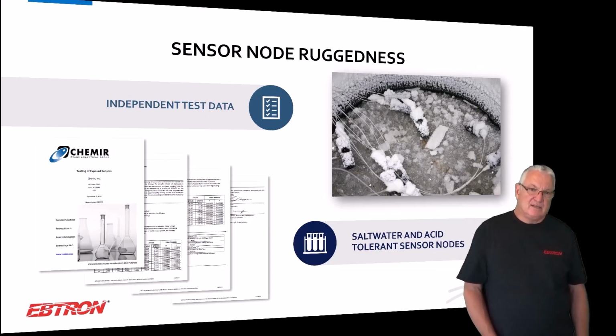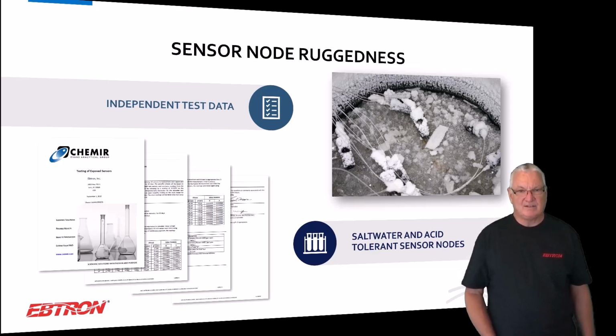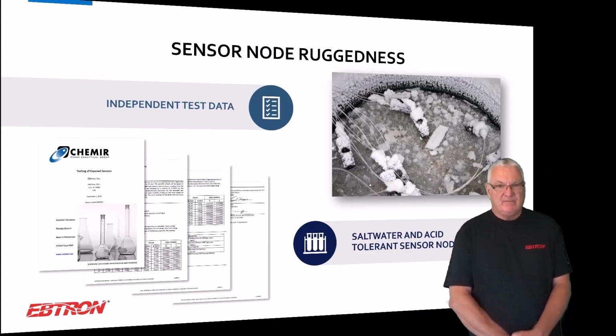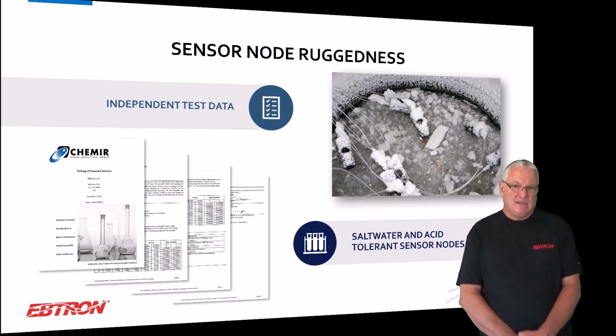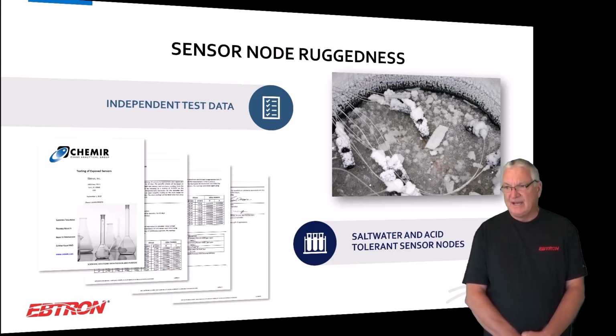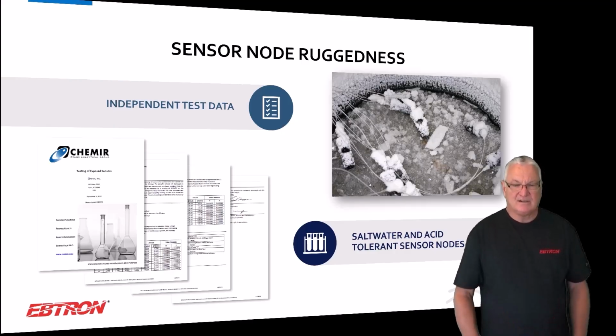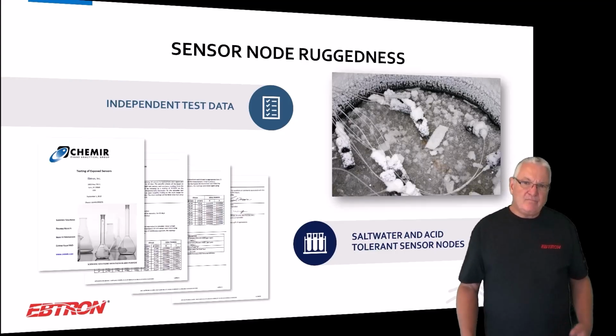I talked about the sensor node ruggedness. I mean, we have the salt water and acid bath study that we sent out for independent testing. It's not just a salt spray test; those are actually sensors that have been put into a heavy salt bath that we've then evaporated the water out of. They have to all pass and function as they did when they were put in. We put these parts over fuming acid baths because we know that things like outdoor air get a lot of salt in the air. We get sulfuric acid in the atmosphere. There's things in the outside air that aren't great. So, that's what we do.